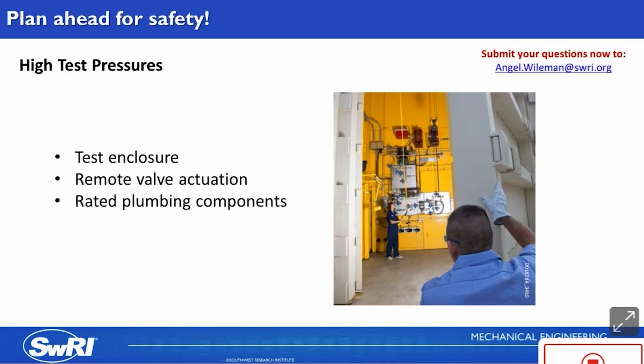All of the components on the setup must be rated for the test pressures. And keep in mind that you're going to temperature extremes and the components will be derated at high temperatures. We also use pressure safety valves, or PSVs, to relieve pressure in case of overpressurization. I would recommend verifying the set pressure of the PSVs by actually testing the PSV prior to performing your fugitive emissions test, and be mindful of the placement of the PSV with the outlet pointing away from sensitive equipment or areas with personnel traffic.